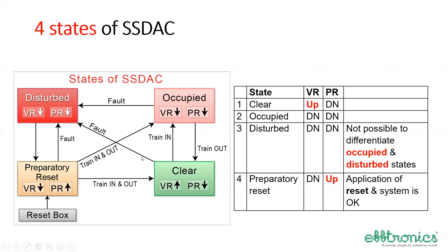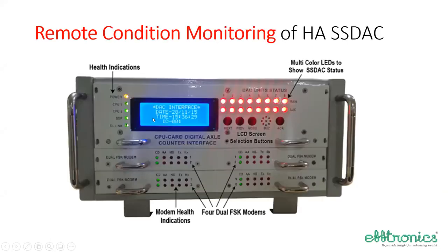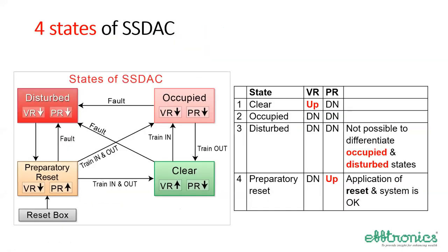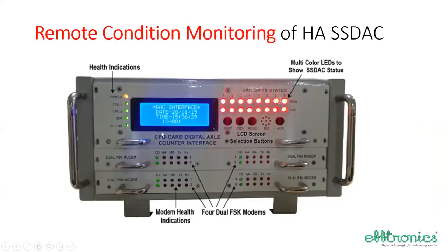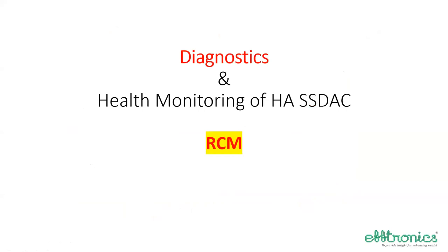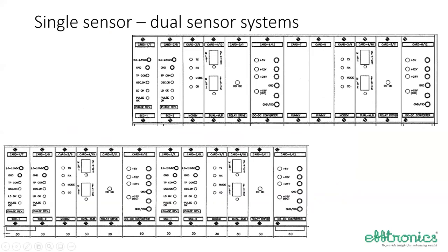Remote condition monitoring of this: we have seen this slide before. We said that between occupied and disturbed we cannot differentiate with the relays, because VR and PR are down in both cases. So with remote condition monitoring, the data available at the station is accessed by another equipment and brought to a central place so that it can be shown to the users, that is the maintenance people. Whatever error codes are shown are available only in the CPUs provided at the station.